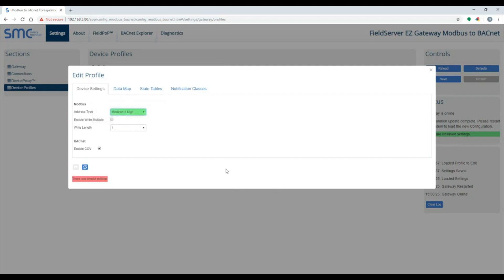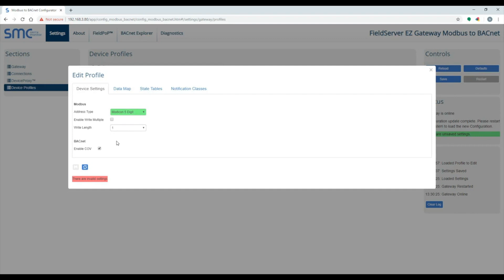Some Modbus devices require function code 15 or 16. To enable this, click on the Enable Write Multiple checkbox. You can also enable or disable COV, which is Change of Value Notifications in BACnet.